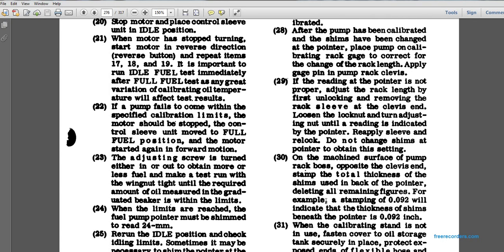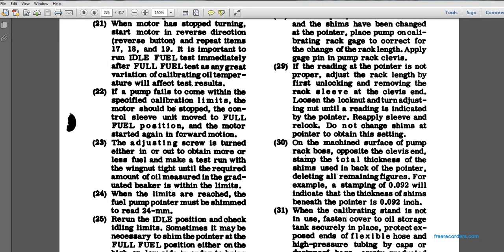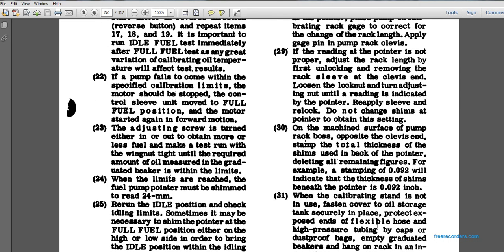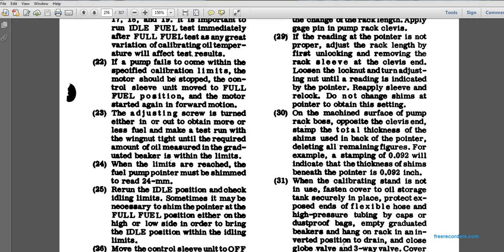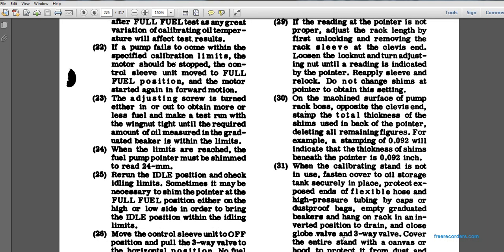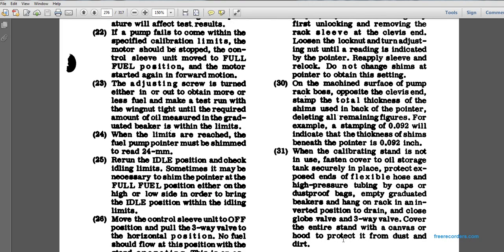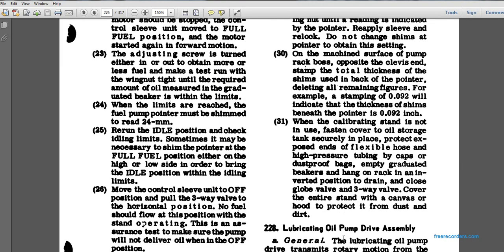When the calibration stand is not in use, fasten the cover to the oil storage tank securely in place. Protect exposed ends of the flexible hoses and high pressure tubing with caps or dustproof bags. Empty graduated beakers and hang them on the rack in the inverted position to drain. Close the globe valve and three-way valve. Cover the entire stand with a canvas hood to protect it from dust and dirt.